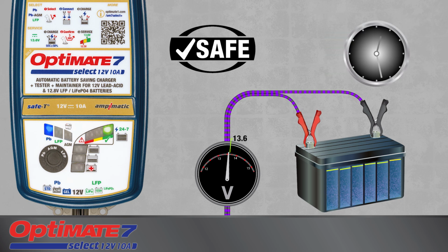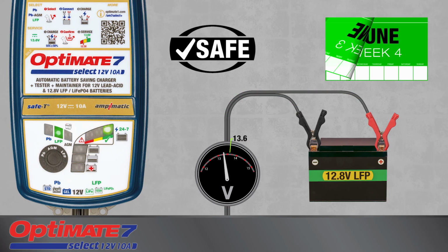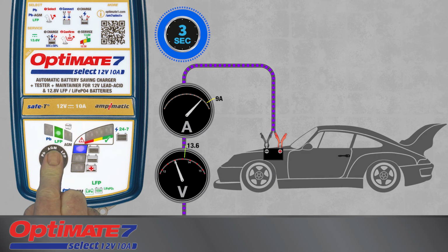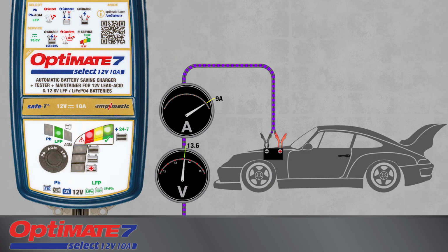For PB or AGM modes, the battery receives an hourly float charge, alternating with a rest period. This ensures the battery remains at 100% full charge, as recommended for lead-acid batteries. In LFP mode, the battery receives a float charge periodically to keep it within the recommended state of charge range for lithium batteries. The service mode can be selected when the battery is being charged. Once selected, a fixed voltage at maximum current is delivered to support the battery in the vehicle, useful for troubleshooting or adjusting settings when the engine is not running. When the service mode is cancelled, charging resumes in the previously selected battery mode.